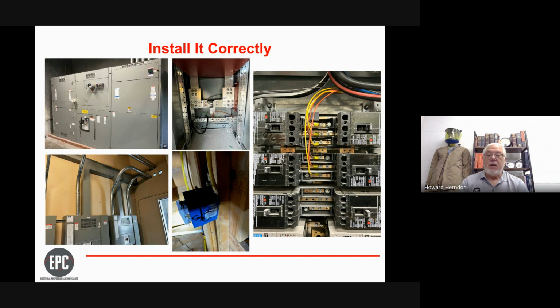The one all the way on the right is, well, I don't have enough circuit breakers in this piece of equipment, so I'm going to do what we might call a tap. This is an illegal tap. It's not approved by the National Electric Code and the procedures they use. Yes, it looks nice and clean, but I do not have any protection on those conductors leaving that panel board.